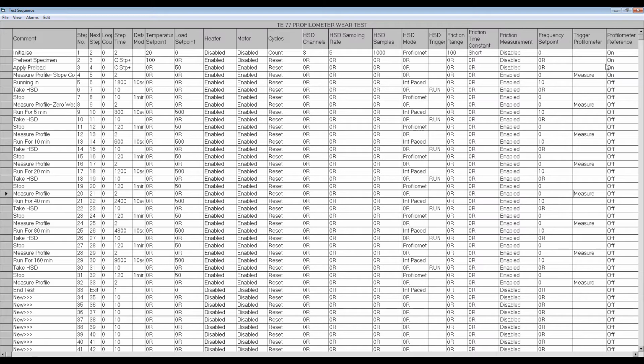Under no circumstances press the Next Step button on the control panel to override the test sequence while a profile measurement is underway. Depending on the action programmed in the next step, this action could potentially cause the moving specimen carrier to crash into the profilometer stylus. The profilometer reference column is set to on for the first measurement and then set to off for subsequent measurements. Note that the HSD mode column is set to profilometer before steps where the profilometer is to be triggered, and to internally paced for steps where high-speed data is to be triggered.